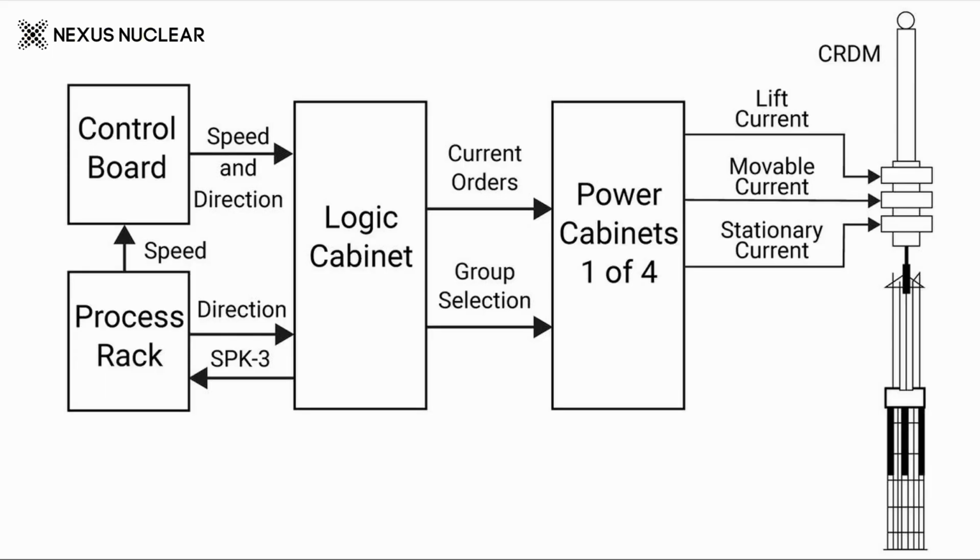As we have seen in the architecture, the supply for these coils comes from a rod control power cabinet. This rod control power cabinet converts the AC into pulsating DC. This DC energy is supplied to these coils, so these coils are energizing. The energizing sequence depends upon the actions to be done on the rod control assembly.